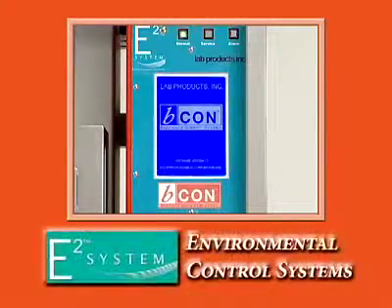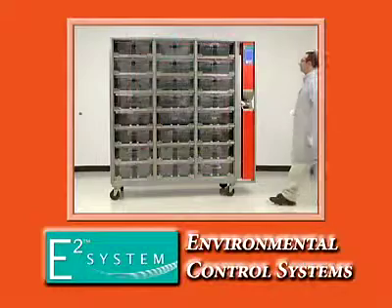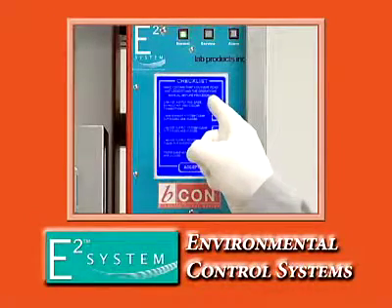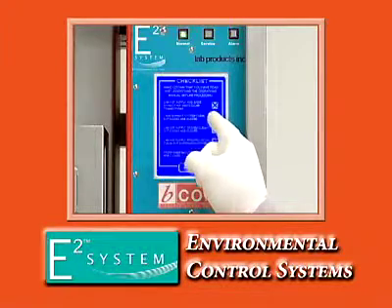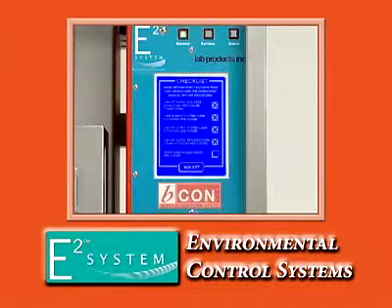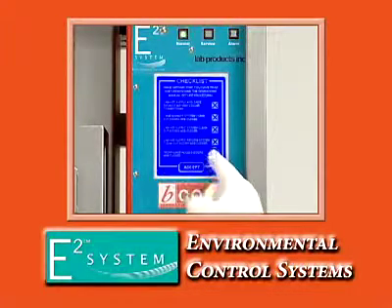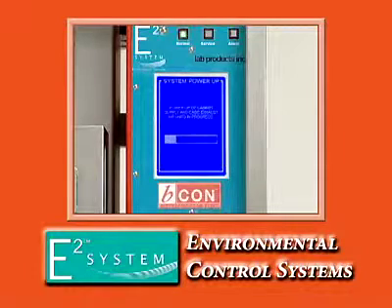Interfaced through a touch screen control panel, the next generation EnviroGuard E2 cabinet supply and cage exhaust units deliver HEPA-filtered airflow that is 99.99% efficient to 0.3 micron particles. Operational parameters are continuously monitored and include cage air changes, cabinet airflow, air pressure, temperature, humidity, fan performance, and HEPA filter hours.